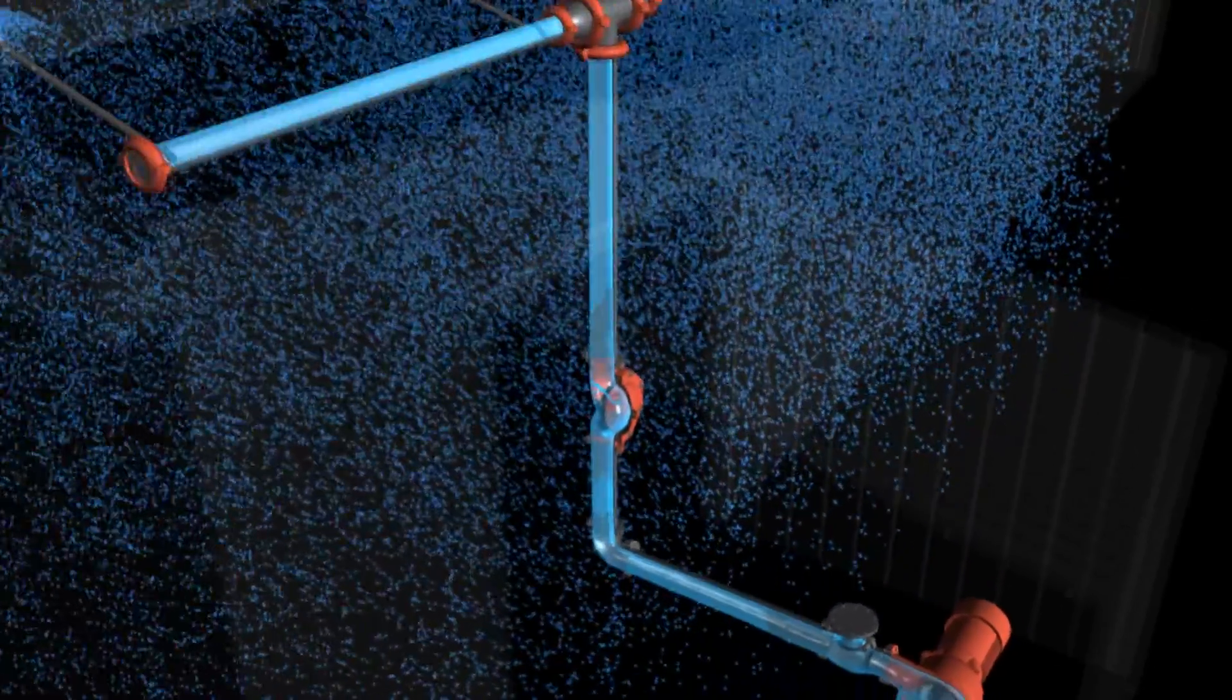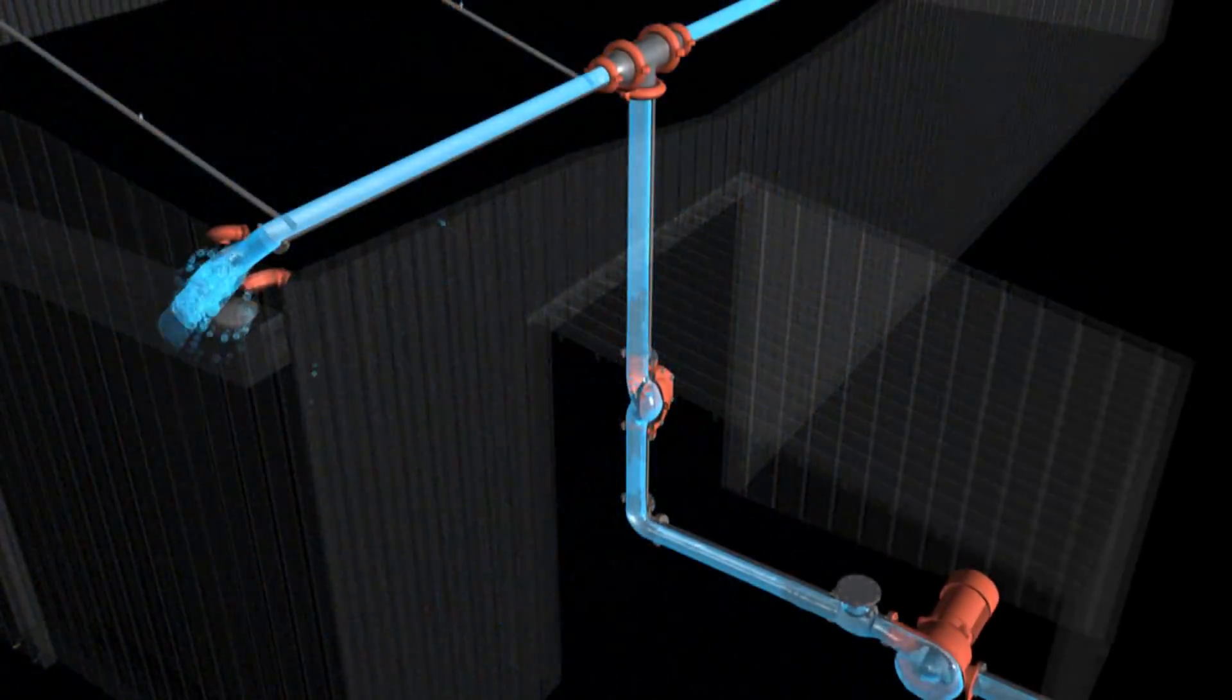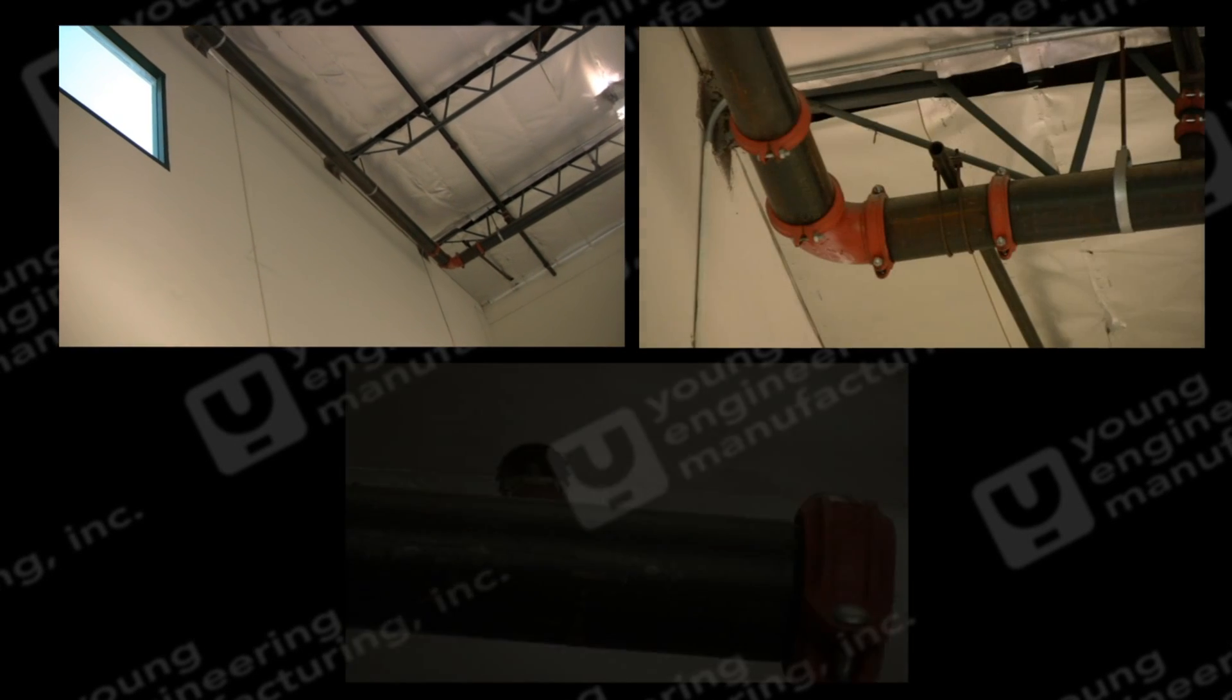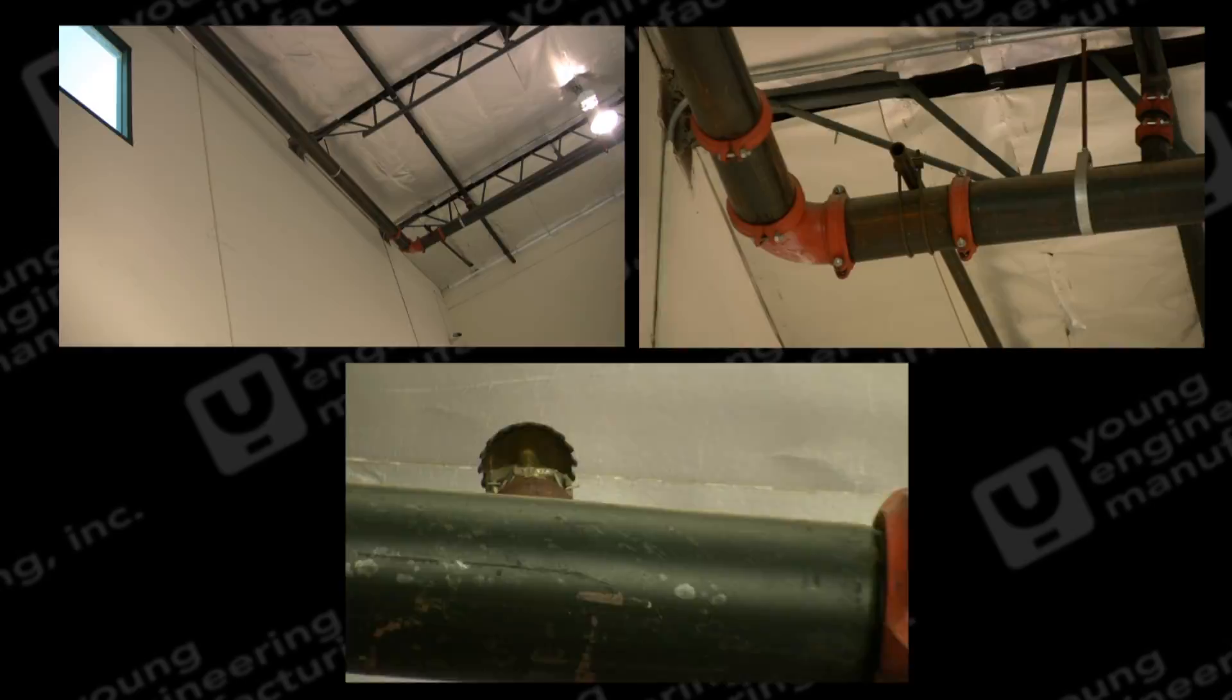This pump pressure can create another surge condition which could potentially cause damage to sprinkler heads and create ruptures at overstressed points in the system.